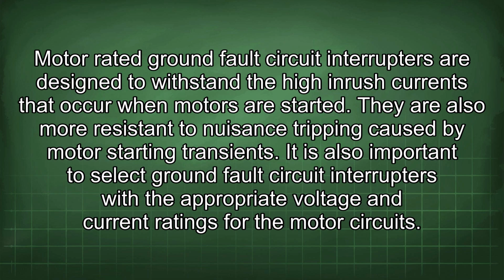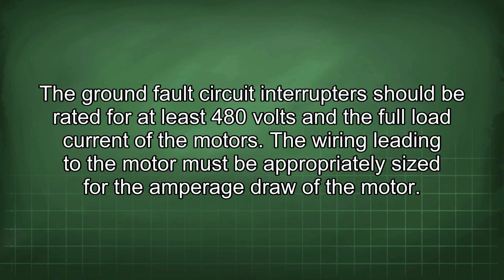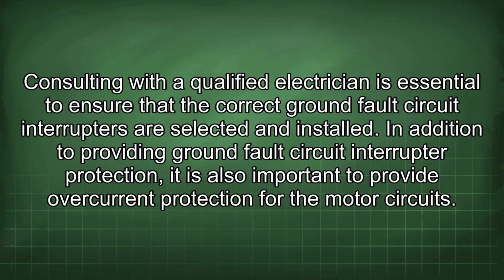Motor-rated ground fault circuit interrupters are designed to withstand the high inrush currents that occur when motors are started. They are also more resistant to nuisance tripping caused by motor starting transients. It is also important to select ground fault circuit interrupters with the appropriate voltage and current ratings for the motor circuits. The ground fault circuit interrupters should be rated for at least 480 volts and the full load current of the motors. The wiring leading to the motor must be appropriately sized for the amperage draw of the motor. Consulting with a qualified electrician is essential to ensure that the correct ground fault circuit interrupters are selected and installed.